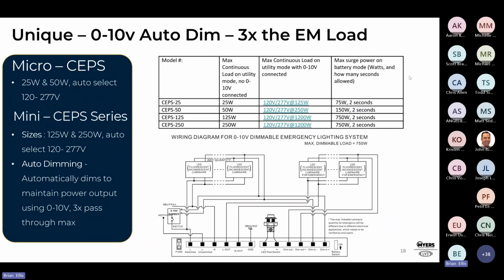If you're utilizing every other fixture in that space, well, that's fine. The other benefit of using this product is, now what if we did every single fixture in the corridor stairwell as emergency? So now I could have 750 watts of total lighting, normal and emergency. And then I could utilize my 125, right? Because now I have more fixtures that are emergency. So I can supply less light output per fixture. So I can put the 125 on the 750, right? And dim that down. Now the whole corridor is emergency.